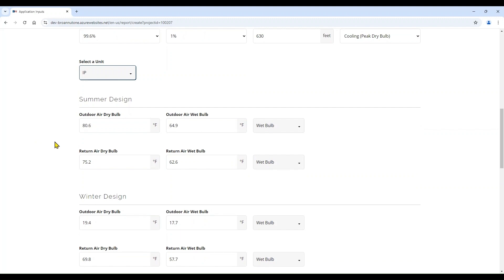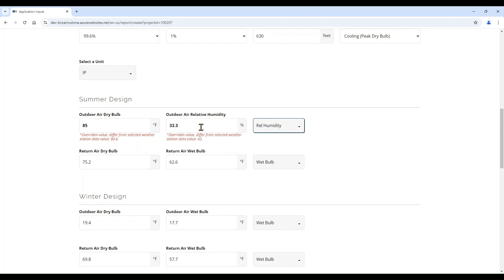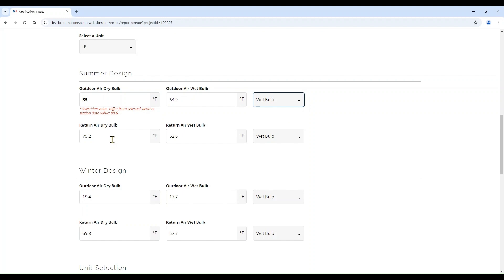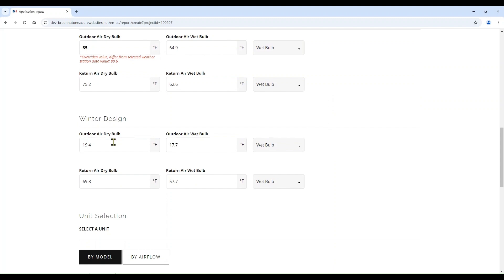With the project location entered, you will now see your summer design and winter design conditions based on the project location and weather station selected. These fields have been pre-populated, but you do have the ability to change these based on your application needs. When you change a value, you will see a message indicating that this value is being overridden from what the weather station provides. You also have the ability to change the outdoor conditions from wet bulb to relative humidity, and you can override this condition as needed. You can also change your return air conditions and relative humidity, entering both your summer design data and winter design data.